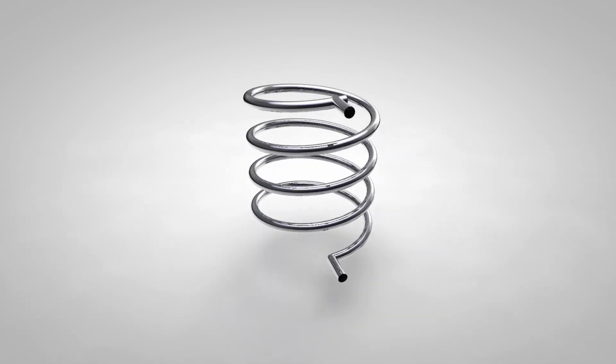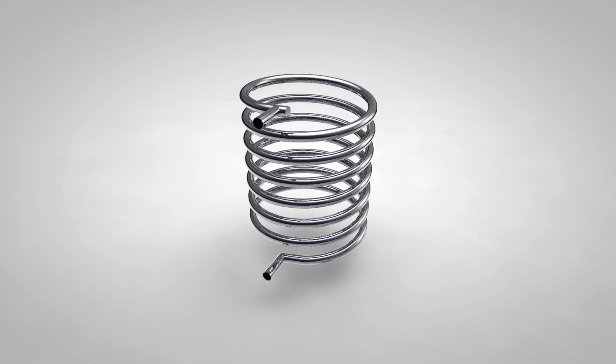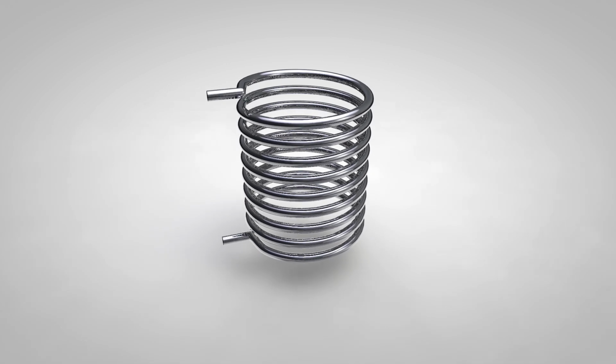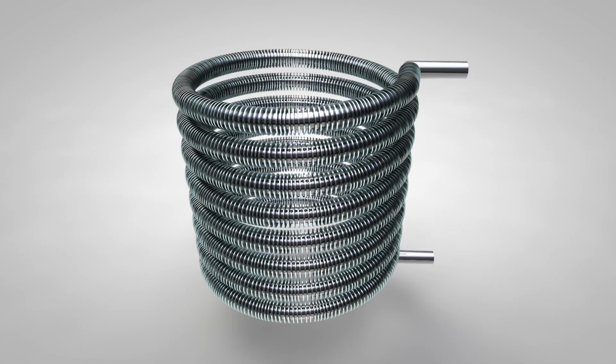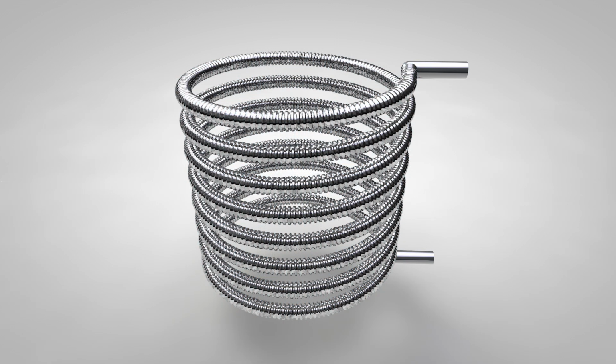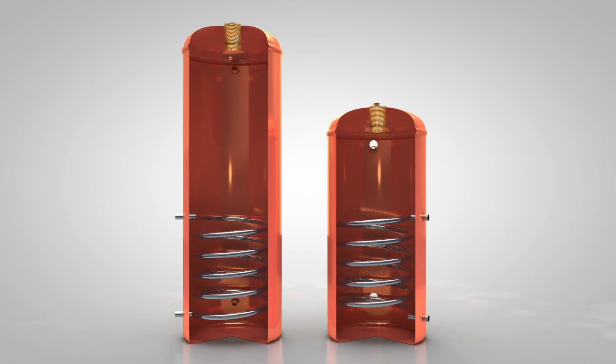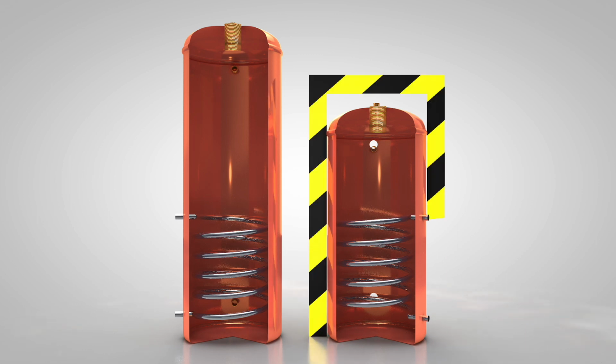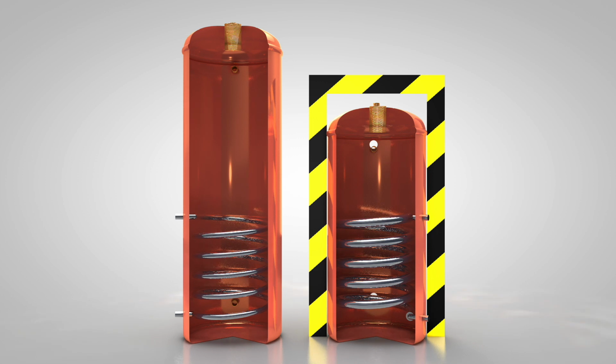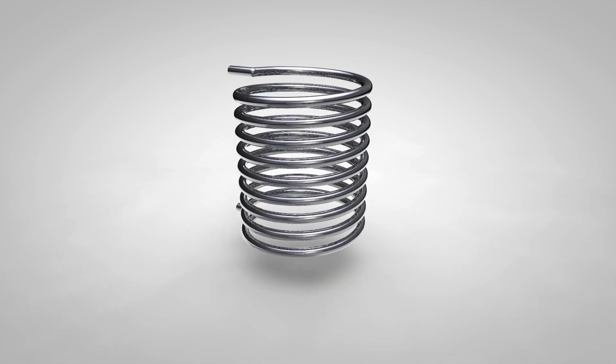Having a large coil surface area and a high kilowatt rating is important for heat pump cylinders because they work at relatively lower temperatures compared to a conventional boiler, meaning the coil needs to transfer as much heat as possible. High kilowatt ratings are also essential for thermal stores and are most often used in copper cylinders to compensate for when an undersized cylinder is used due to insufficient space, to help achieve the required volume of hot water with a faster heat-up time.